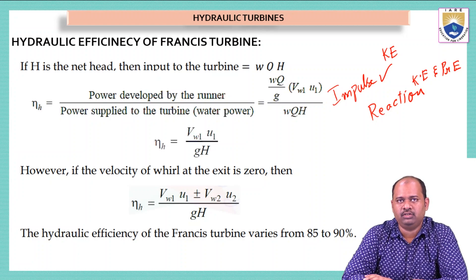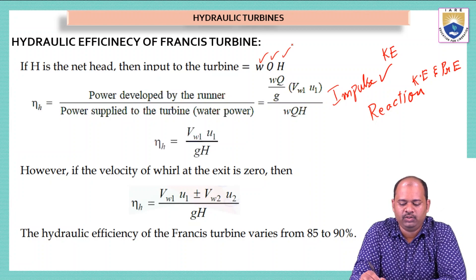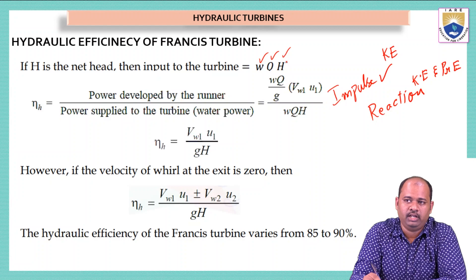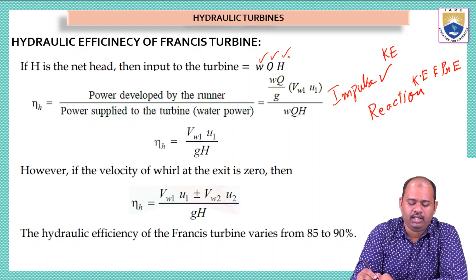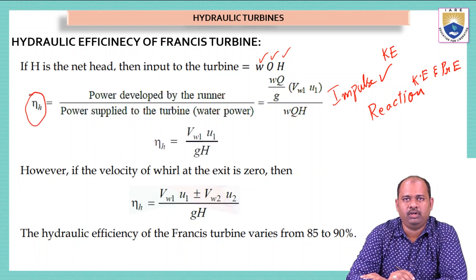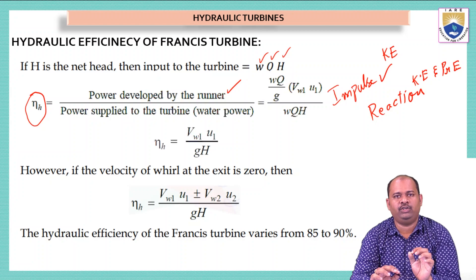If capital H is the net head, then the input of the turbine is equal to W×Q×H, where W is the weight of the water, Q is the discharge of water coming out of the turbine, and H is the net head of the turbine. When we calculate efficiency, hydraulic efficiency is equal to power developed by the runner divided by power supplied to the turbine. We have two types of powers, and using these we can calculate the hydraulic efficiency.